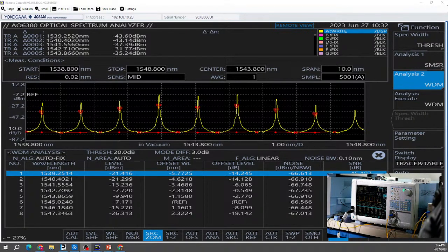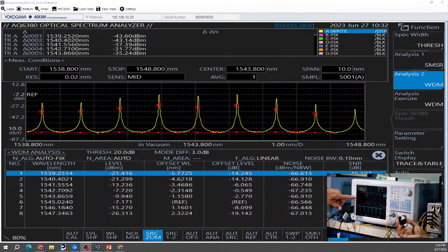Can I connect my keyboard or mouse onto the OSA? Yes. So you have the mouse, as Daniel pointed out, and you can click on this screen. This is what they call WYSIWYG: what you see is what you get. You see a parameter just like how we're touching it. I don't know if you can see well enough, but there are boxes that show sensitivity, resolution.